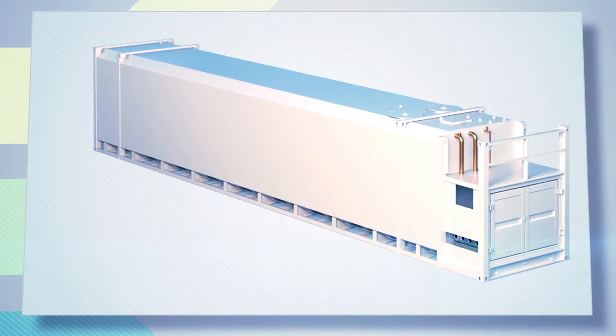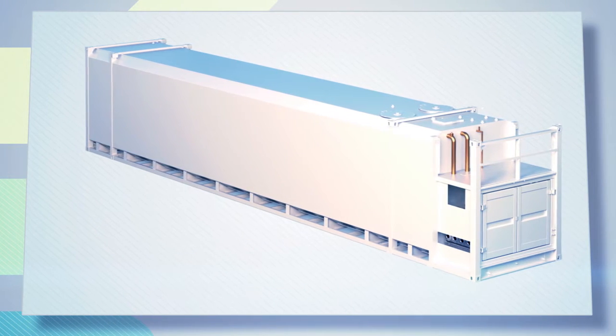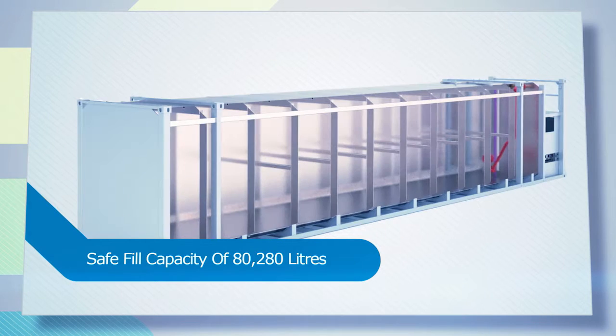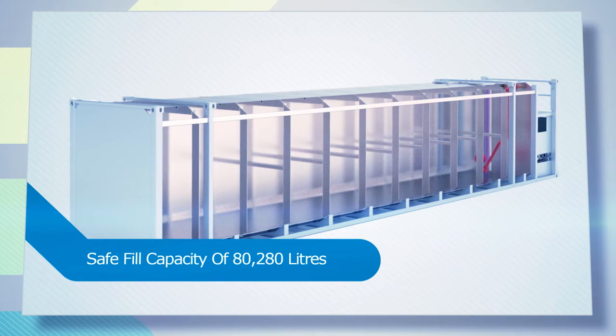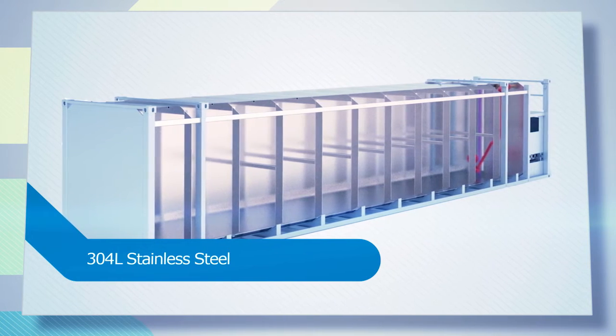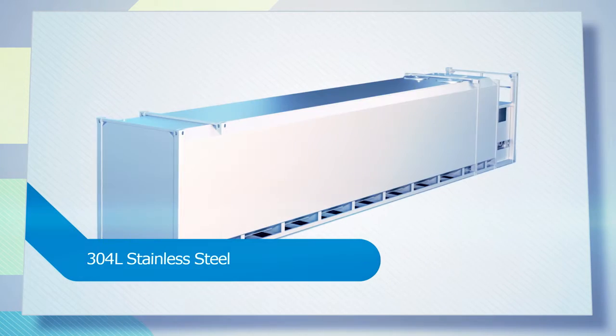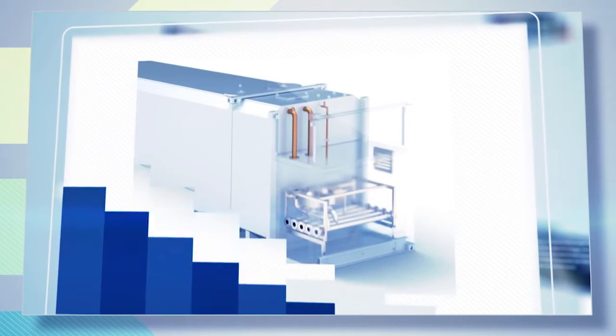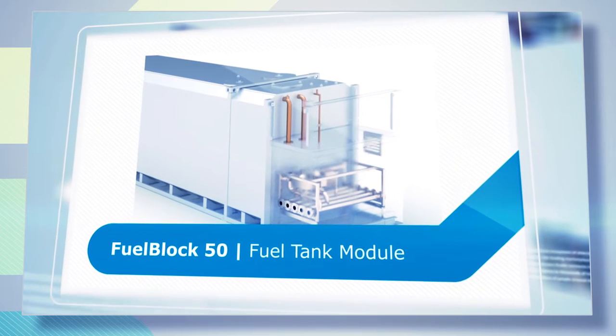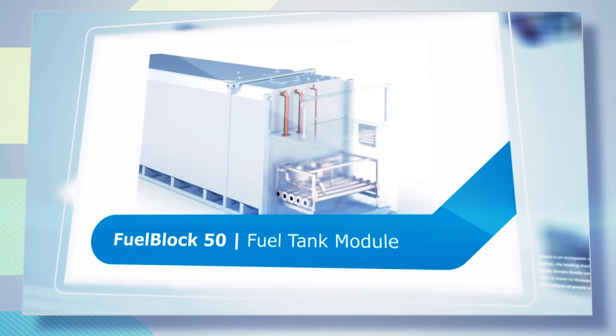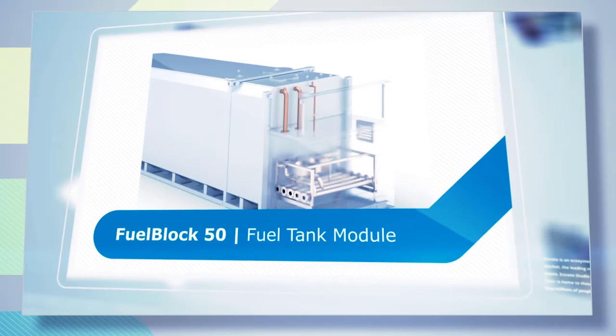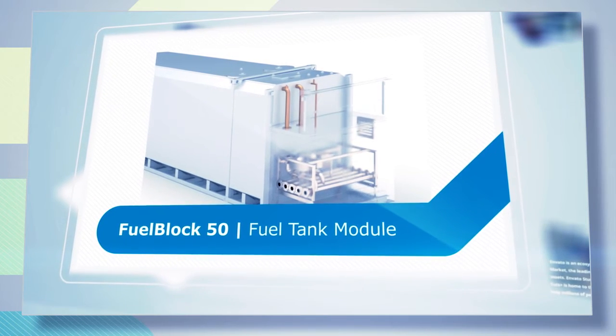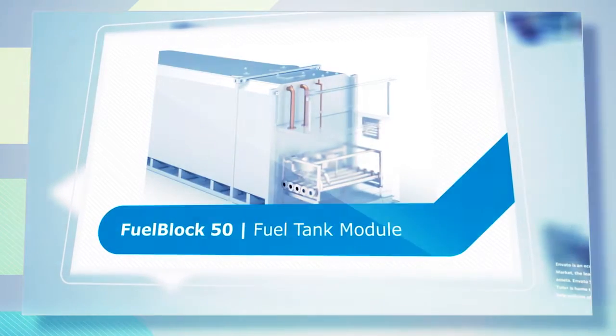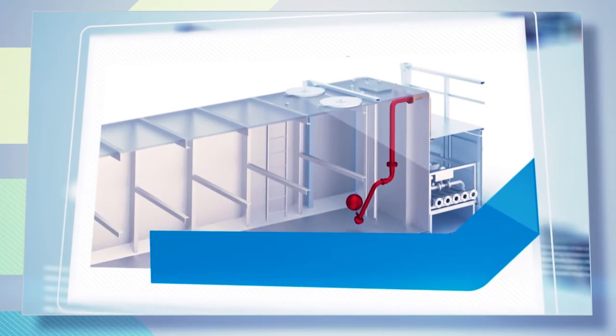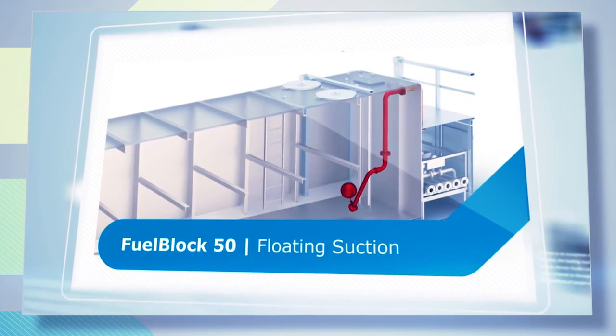The fuel tanks are a self-bunded double-wall design with a safe fill capacity of 80,280 litres. All internal plates and members are 304L stainless steel. Pre-assembled modules complete with piping and actuated valves are installed in the fuel tank valve bay. Level instrumentation is fitted to the tank and easily connects to pre-wired sockets at the module terminal box. A floating suction line ensures the pump suction is suspended in the upper fuel inventory.